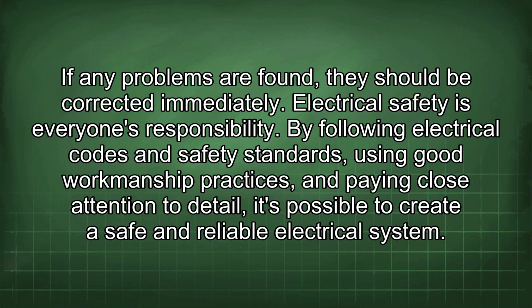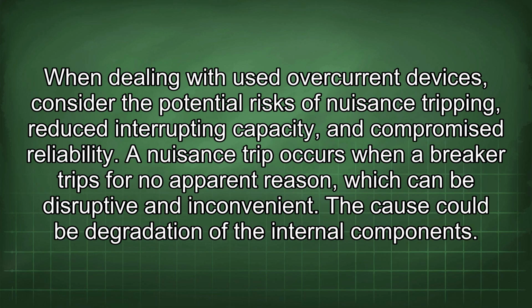Electrical safety is everyone's responsibility. By following electrical codes and safety standards, using good workmanship practices, and paying close attention to detail, it's possible to create a safe and reliable electrical system. When dealing with used overcurrent devices, consider the potential risks of nuisance tripping, reduced interrupting capacity, and compromised reliability. A nuisance trip occurs when a breaker trips for no apparent reason, which can be disruptive and inconvenient. The cause could be degradation of the internal components.